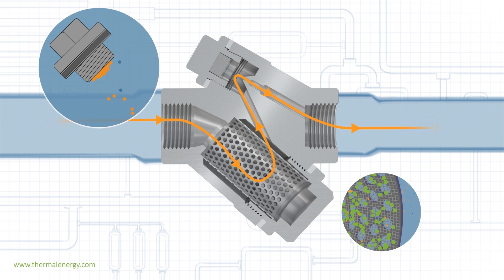Our magnetic cap is strategically placed to cover the full cross-section of the orifice. As the fluid flows towards the orifice, the magnet attracts the magnetic particles, preventing them reaching the orifice. When safely isolated, the magnetic cap can be inspected while the trap remains in line. The debris collected can be easily removed from the magnet, and the cap reapplied.